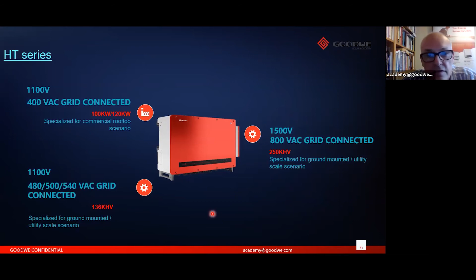So here are some features of the HT series, which are going to help reduce costs. One of those features is that we do have built-in surge protection devices, and these come in a standard type 2, but if that isn't sufficient for the scenario, you can upgrade these to a type 1. So what that means is you don't have to go to the additional cost of adding any additional string protection boxes out there. So less time, less cost. It's all within the inverter itself.